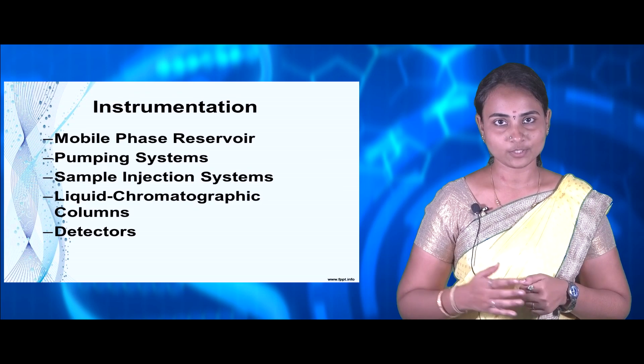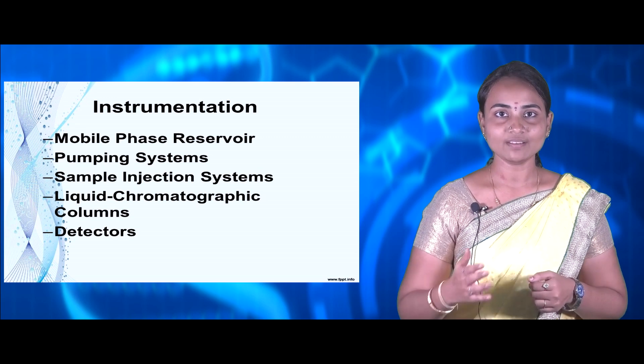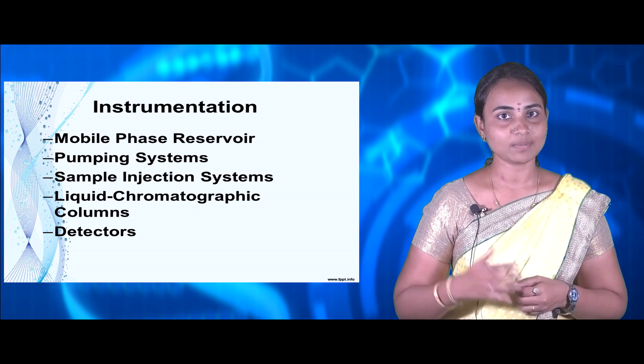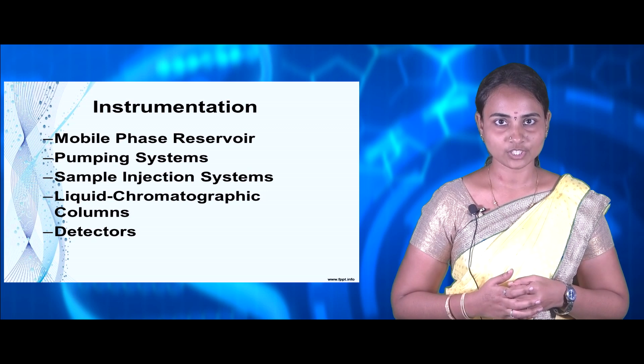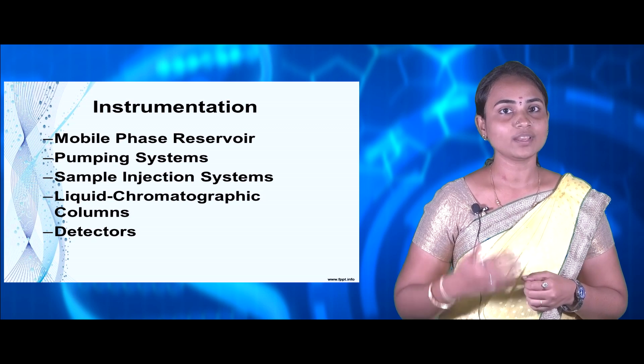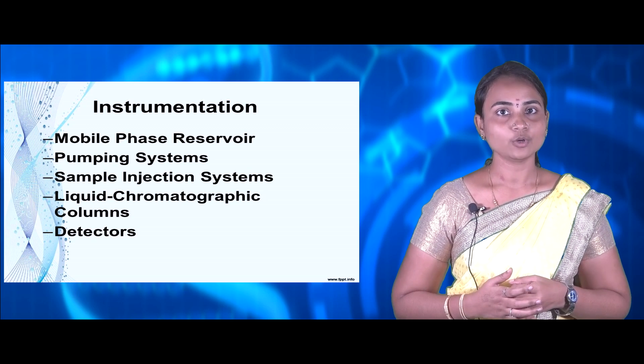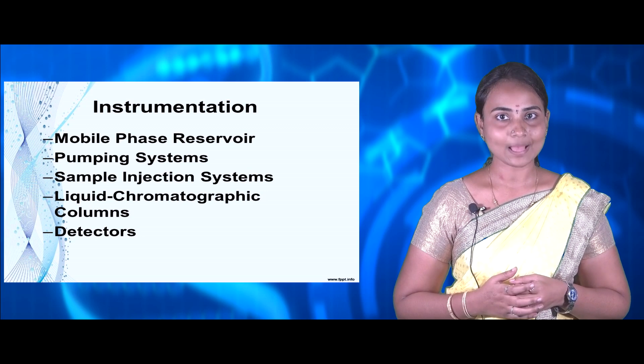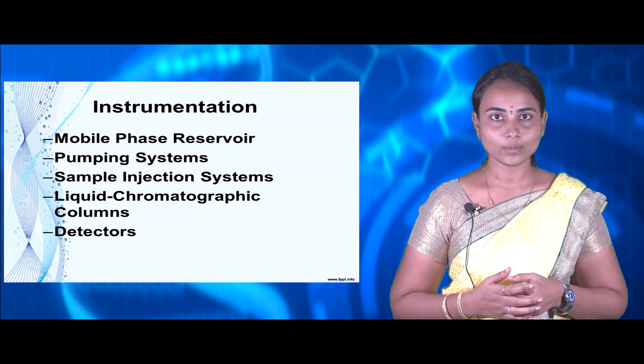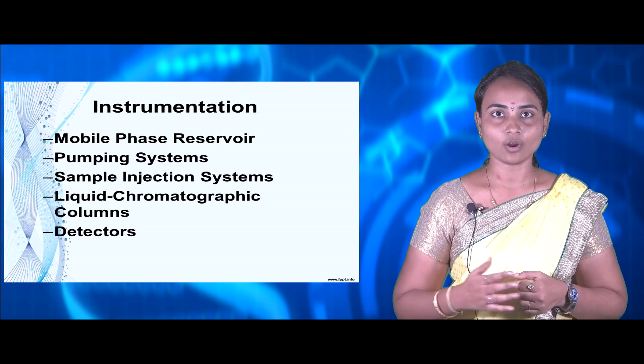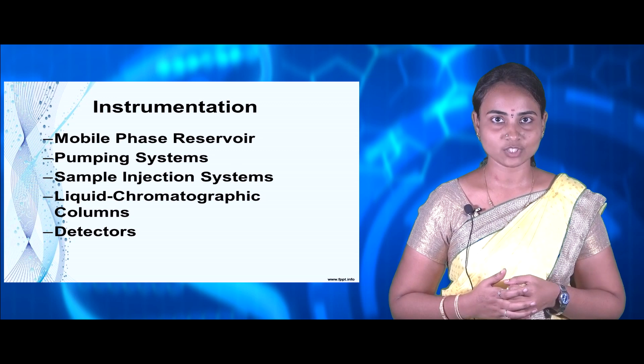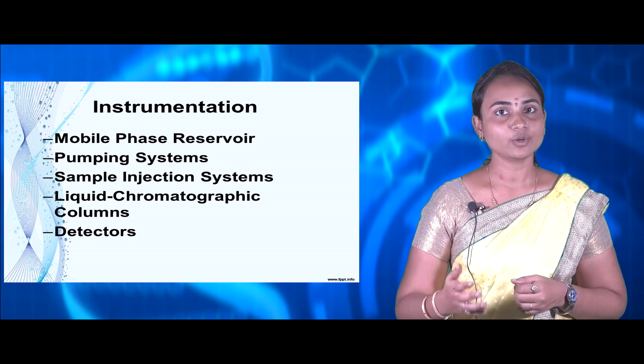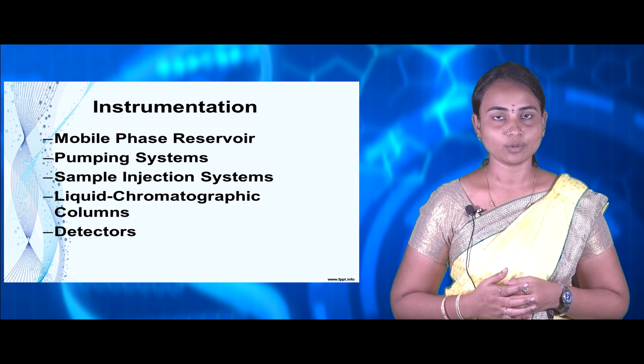Coming to the instrumentation of HPLC: it involves a mobile phase reservoir for transferring different solvents based on their composition, a pumping system to apply high pressure to the flow of different solvents, a sample injection system, liquid chromatographic columns for separating components based on their partition behavior, and detectors to produce the final chromatogram.